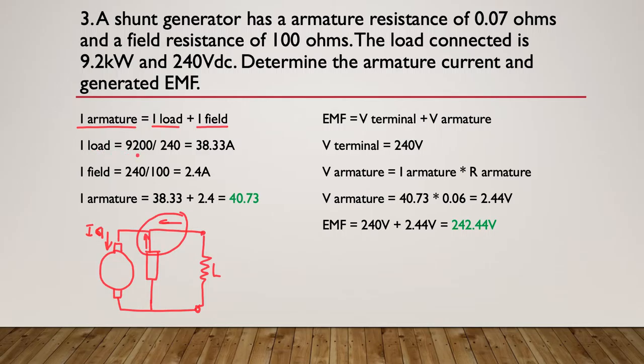So those two added together have to end up being this current here through the armature. Our I load is simply our 9.2 kilowatts divided by our 240, giving me 38.33 amperes. I can work out the current in the field, because again, it's got 240 volts. They tell us it was 100 ohms. So we know that the field here was 100 ohms, and that gives me 2.4. I add the two of them together and I get an answer of 40.73 amps.